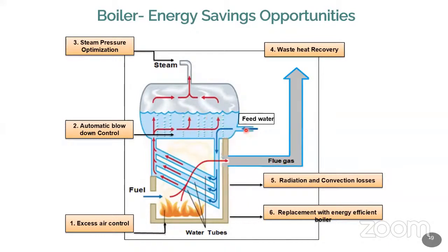Then the feed water is heated with the help of an economizer or some other means. I saw one factory using a solar water heater to heat the water from ambient temperature to nearly 60 to 75 degrees. Then condensate water is also available, so they feed the water at nearly 85 to 90 degrees to the tank. So what is the advantage? You need only a 10 degree rise to heat the water to become steam. So that's another advantage. Okay.